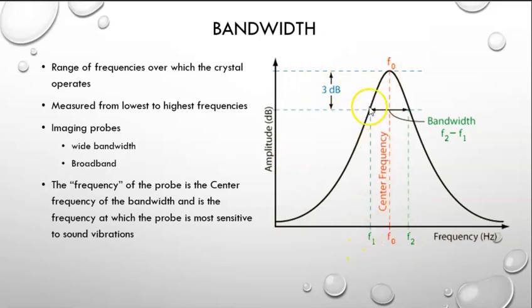This is called the shoulder of the frequency. These are the shoulders, and typically they are a 3 decibel drop in sensitivity. Can they be other numbers? Yes, they can be 6 decibels. So that's just something you'd have to look at, what the manufacturer has determined the bandwidth is set for. All right, let's move on.